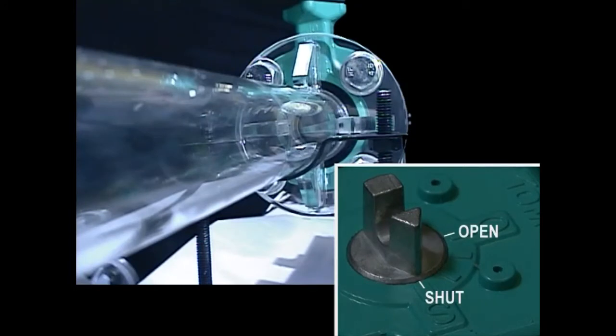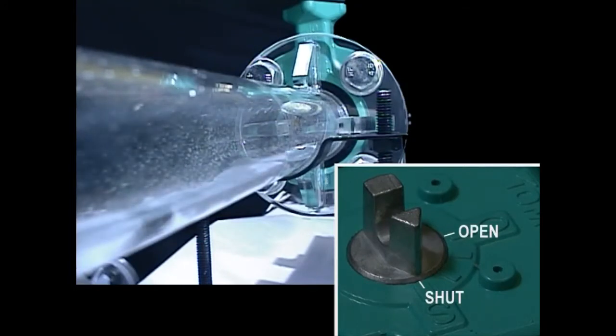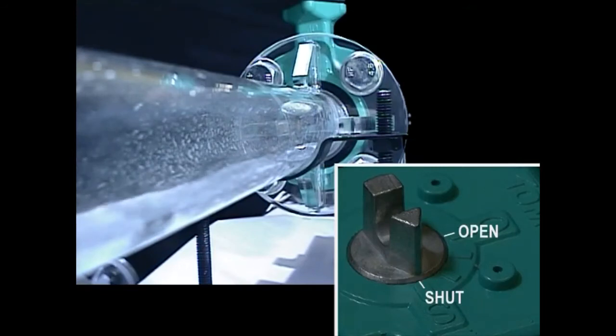With butterfly valves, since flow is not proportional to valve opening, remember that a large quantity of water may flow even if the valve opening is small.